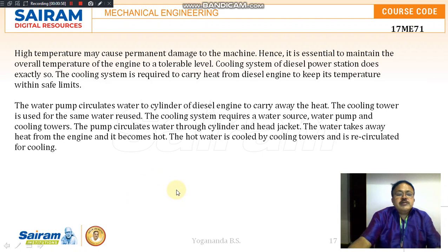High temperature will cause permanent damage to the machine. So it is essential to maintain the overall temperature of the engine to a tolerance limit. The cooling system of this power station will do this job exactly, so that it will carry the heat from the diesel engine to keep its temperature within the safe limits. The water pump will be circulating water to the cylinder of the diesel engine to carry away the heat.